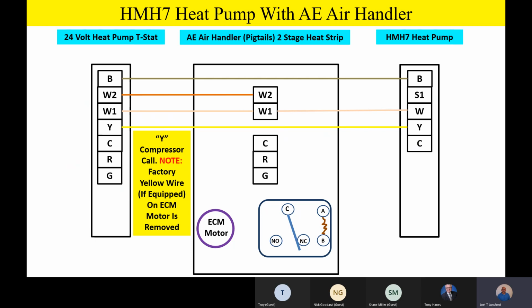You'll also note that on the AE air handler, you may have a yellow factory wire on the ECM motor. If that's the case, be sure and remove that yellow wire from the ECM motor, because we're going to be doing some different things with the speeds on that motor. So if it is equipped with a yellow wire on the ECM motor, please remove that yellow wire from the factory.